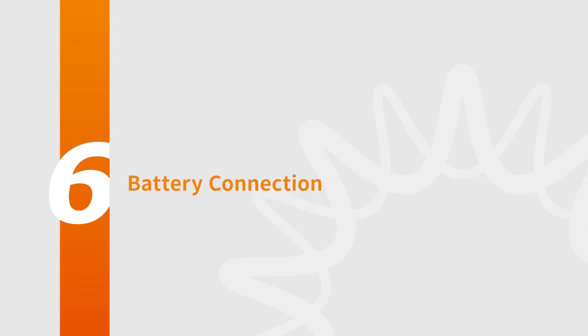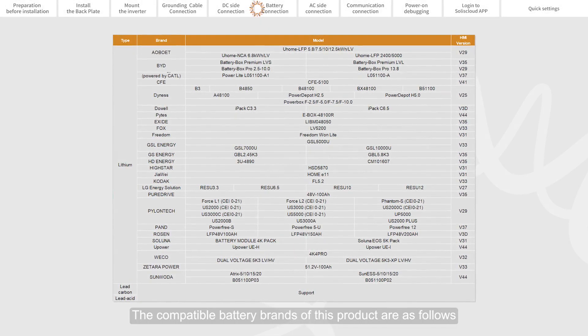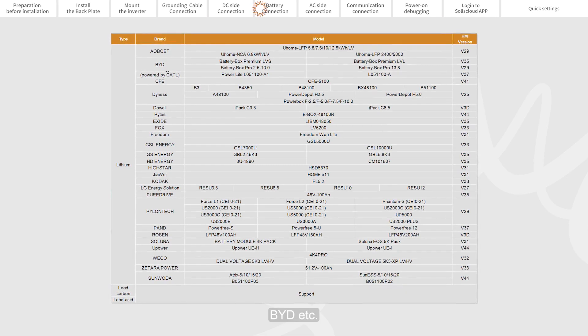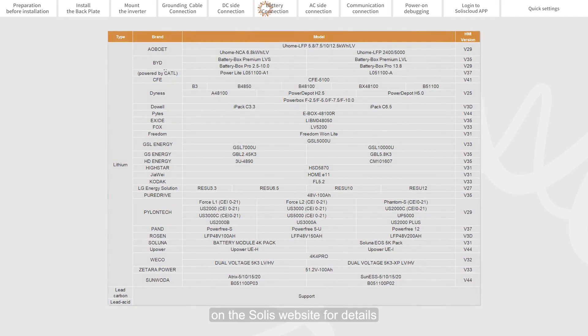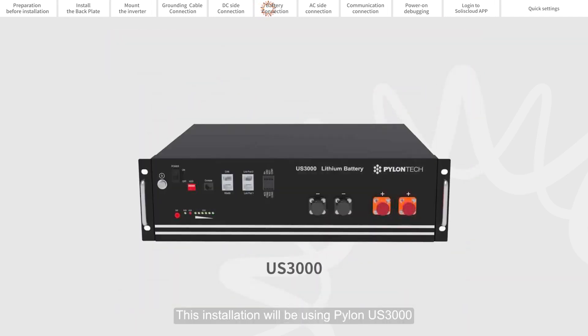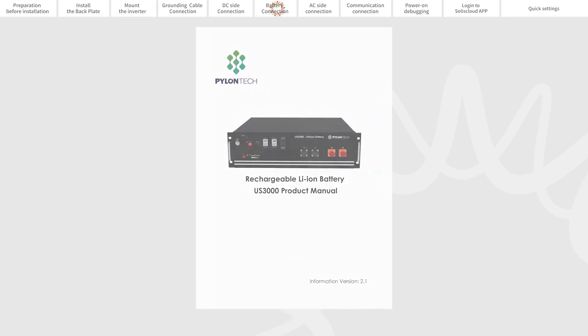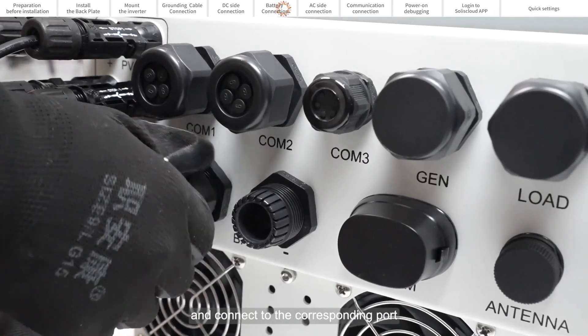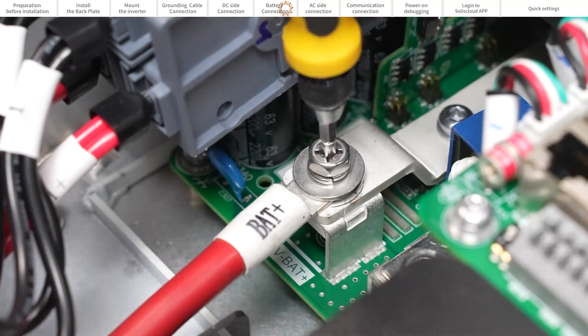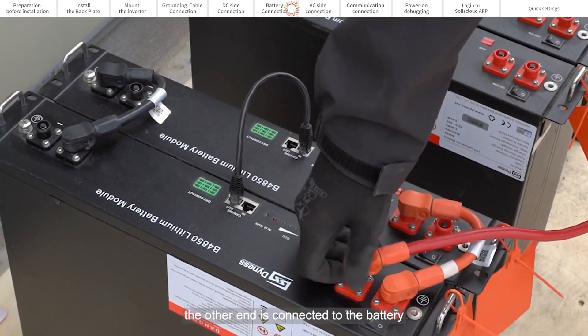Part 6: Battery Connection. The compatible battery brands of this product include Pylon, BYD, and others. Please refer to the battery compatibility list on the Solis website for details. This installation will be using Pylon US3000. For battery installation, please refer to the battery manufacturer's instructions. Pass one end of the battery power cable through the BAT port at the bottom of the inverter and connect it to the corresponding port. The other end is connected to the battery.